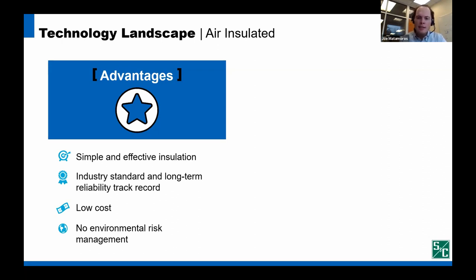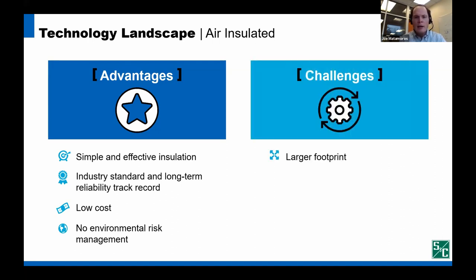Air insulated gear does have challenges in an evolving underground grid. Air insulation requires more space between active parts than other dielectric insulation systems. Accordingly, the product footprint is larger than other technologies. Air insulated gear can't be applied below ground, below grade in areas susceptible to flooding. If you want to keep the switchgear underground and out of the view of the public, then sealed submersible gear should be used.